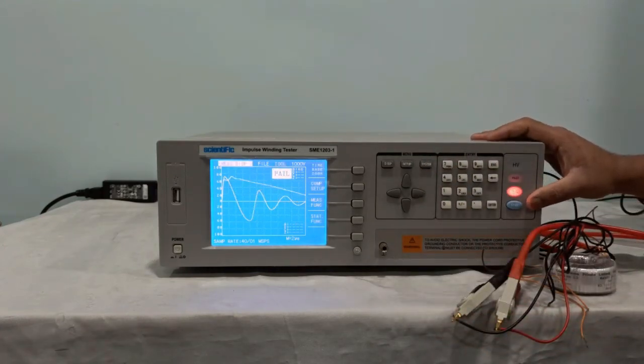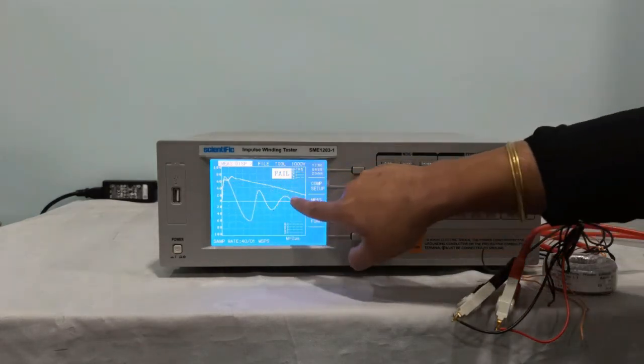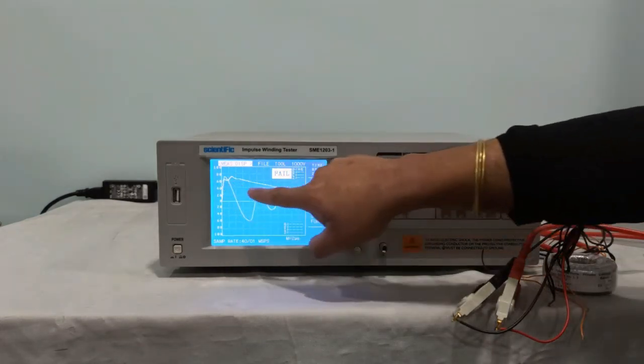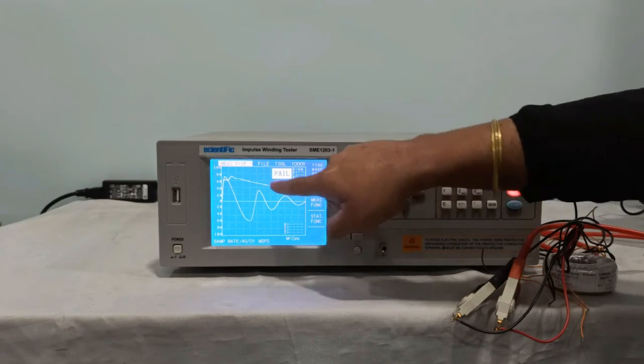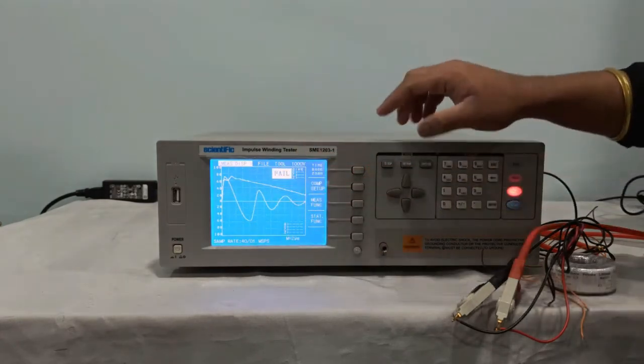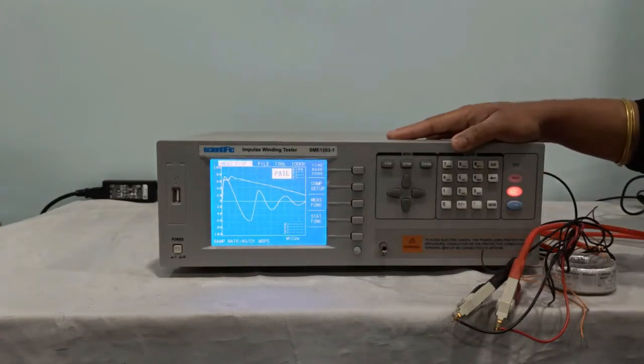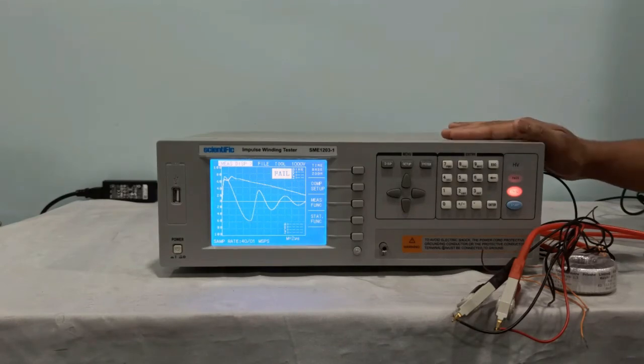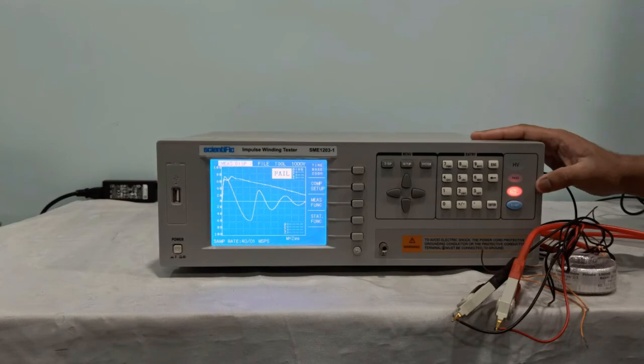Now this is fail. As you can see, this was the standard waveform created by us and this is the tested waveform. Both are different, so the result is fail. So this is how the measurements are done using this impulse winding tester. And you will get the pass fail indication here also. Right now this is fail, so it is glowing in red color. When the result is pass, it will glow here in green color.